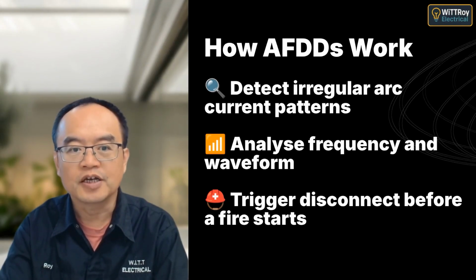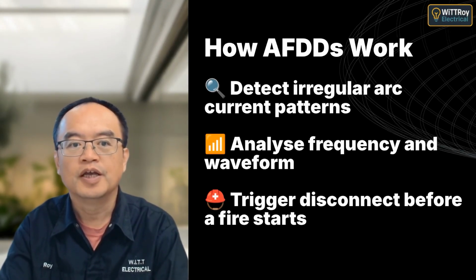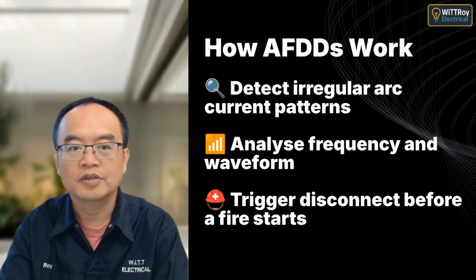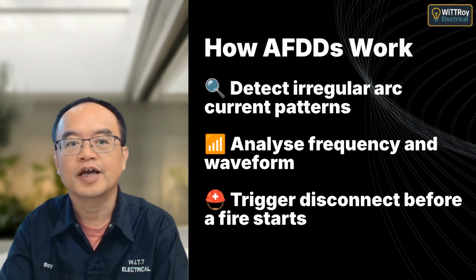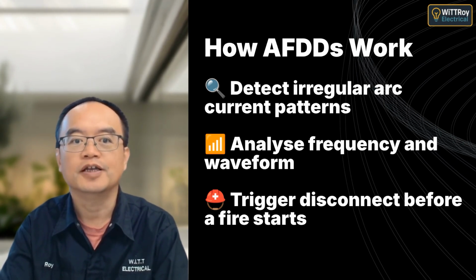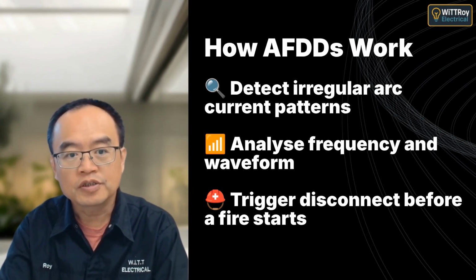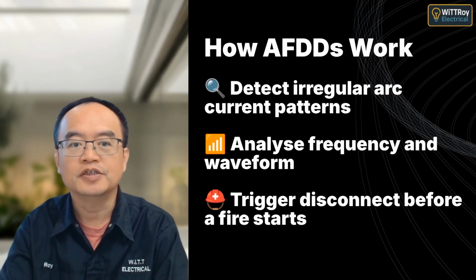AFDDs use advanced electronics to monitor current flow. They identify abnormal arcs based on waveform and noise, and disconnect power before a fire can ignite. They're especially helpful in detecting faults that traditional devices can't catch.